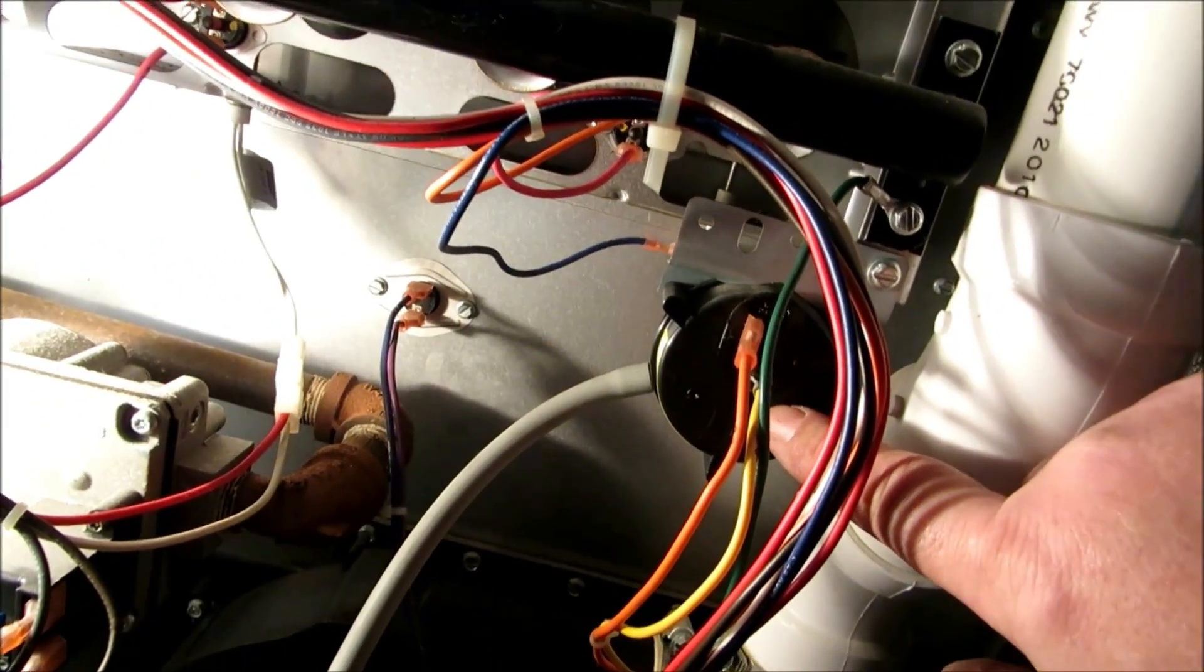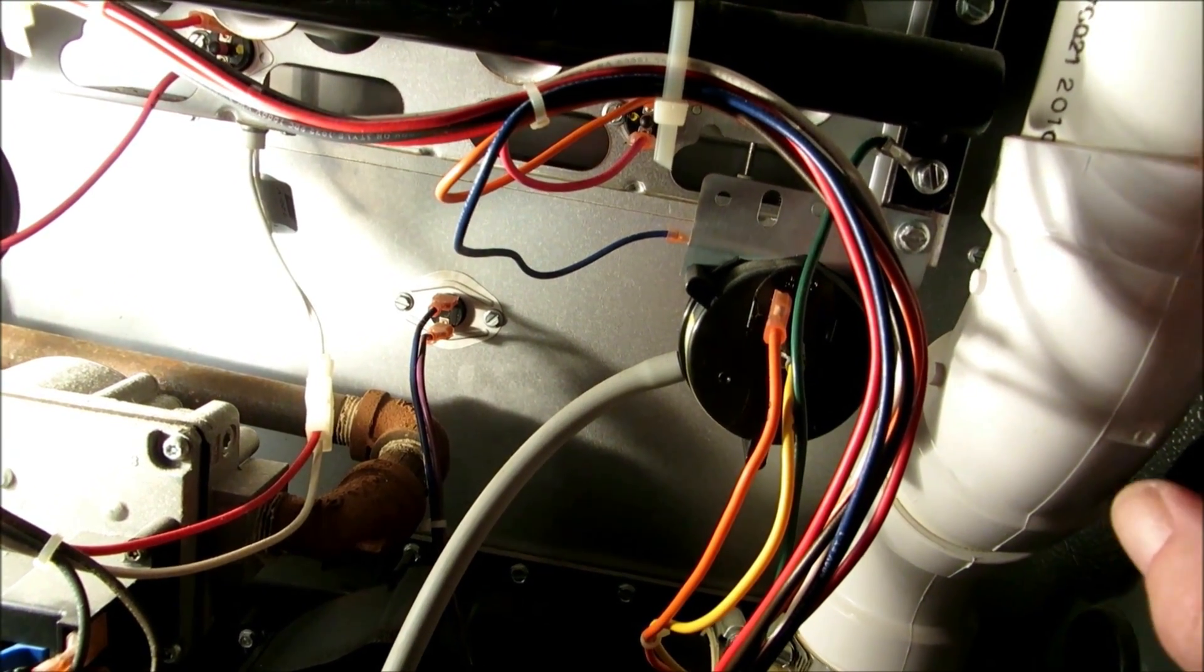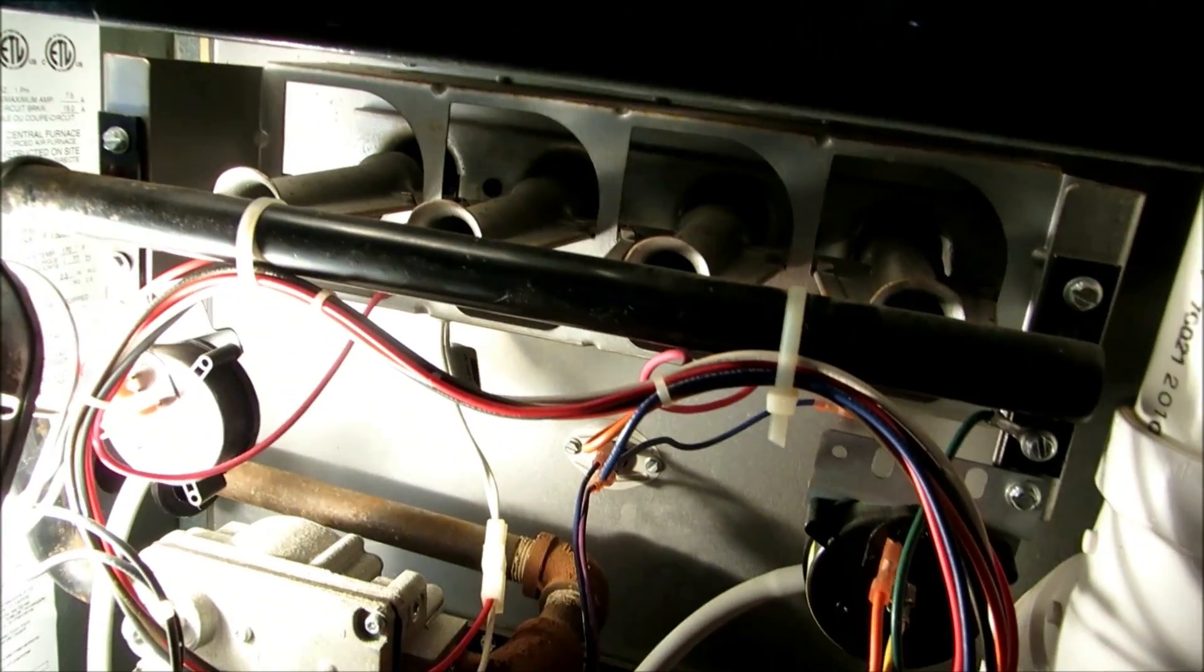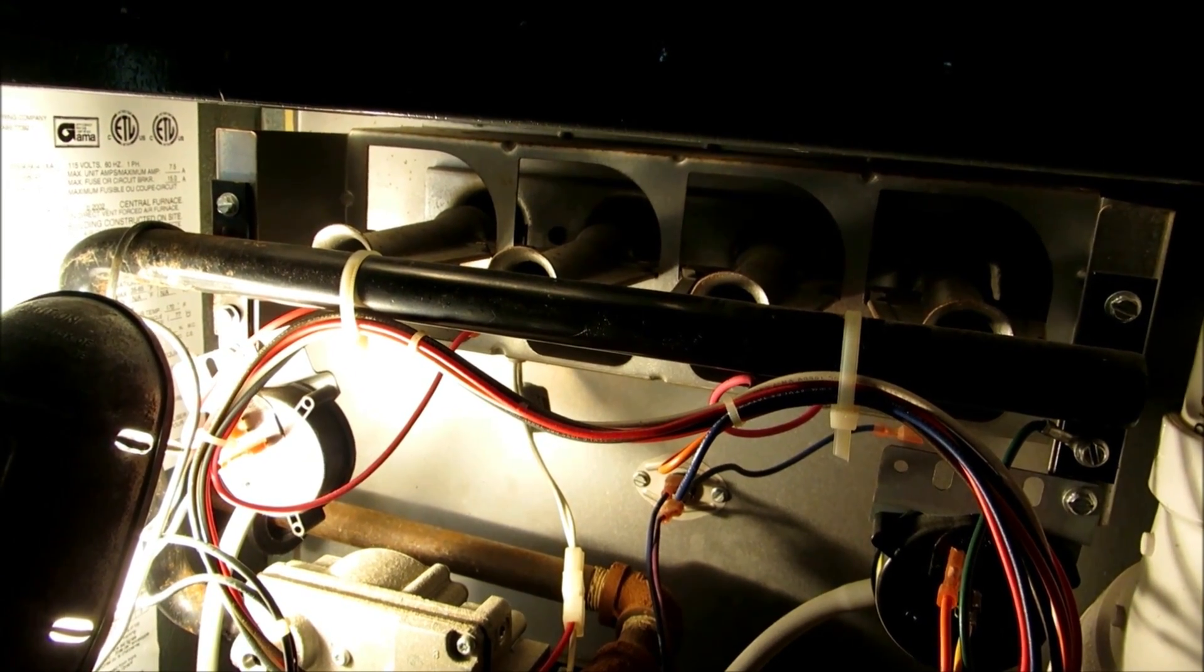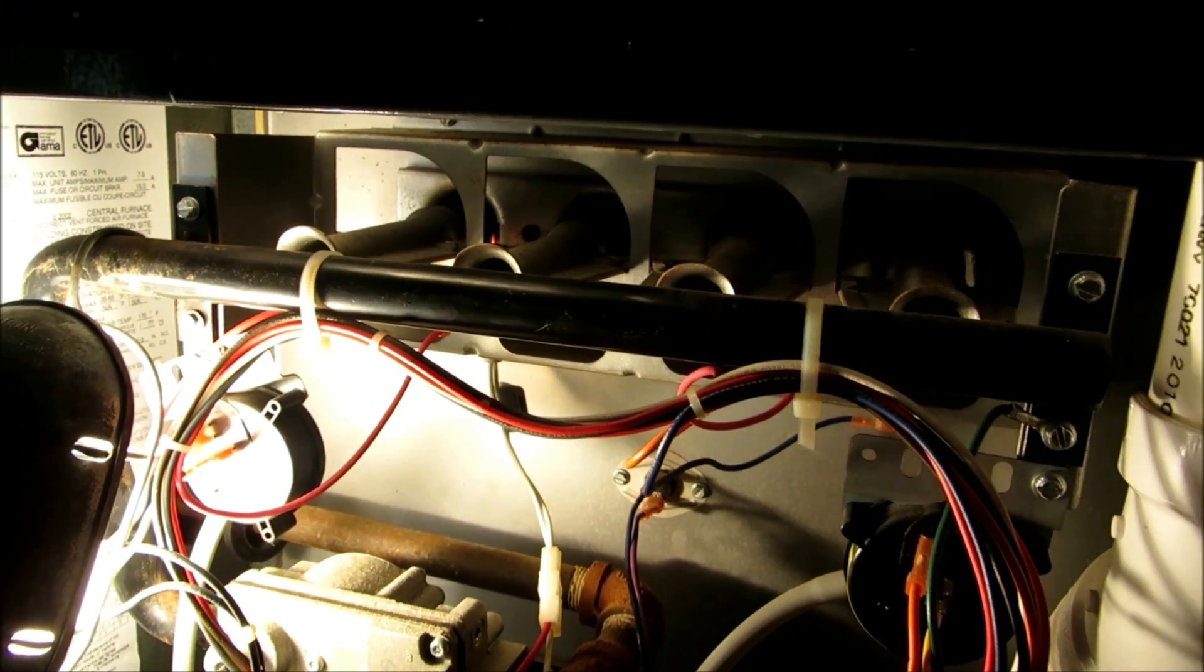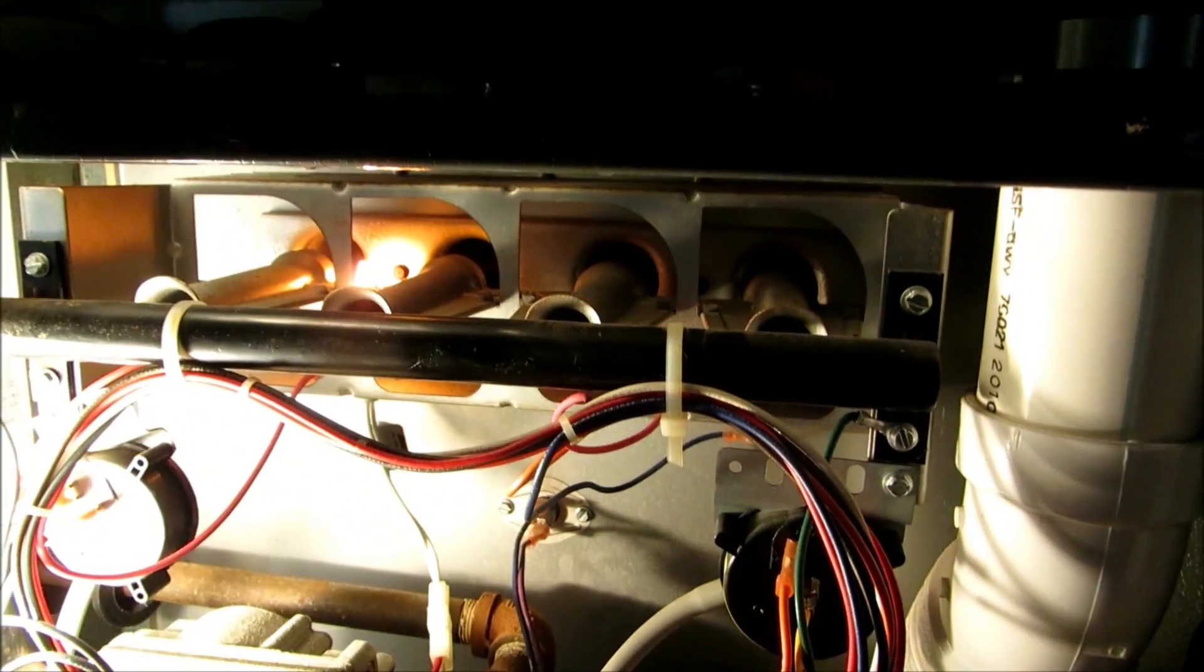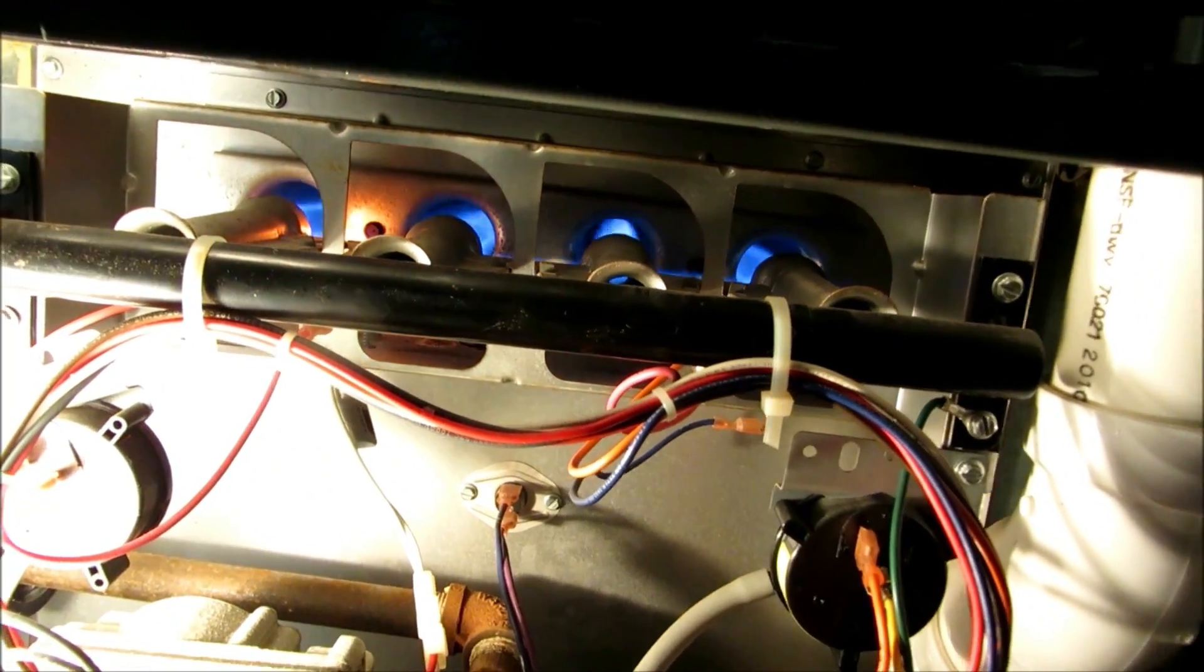Here's our inducer. Next, our pressure switch is going to make and tell the furnace that our vent here is clear. Then we should see a glow here in just a matter of seconds on our igniter. There's our igniter, guys. Within a few seconds, we're going to hear the gas valve click and we're going to see flame patterns will spread. All right, guys. Look at that.